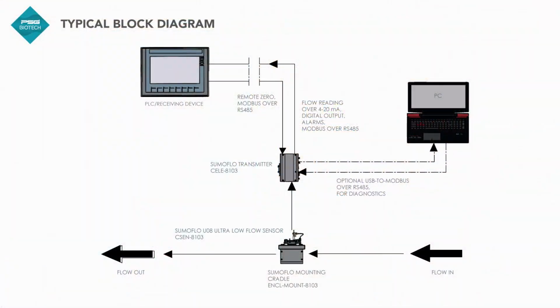It primarily consists of 3 parts: a flow transmitter, which sits in a panel, the electronics, so to speak. And the sensor itself has just a basic coil and a drive coil, etc. All remaining parts are all plastic. It has a memory chip which holds the calibration factor for that particular sensor size, and a mounting cradle to hold it. Since Coriolis is a vibratory type of product, it needs a strong mounting cradle, and that's not disposable. That's permanently installed. So the single-use kit fits into that. That's right.